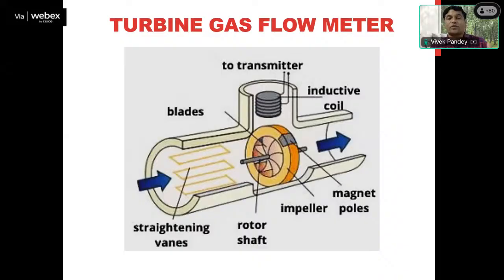And with the gas pressure, the rotor will start rotating, and when the rotor rotates, the magnetic pole will also rotate. And we know very well that when a magnetic pole is rotating, indirectly the magnetic field is rotating, and this magnetic field will interact with the inductive coil connected near the rotor, and that inductive coil will then produce a small voltage, or you can say a voltage pulse. Now these voltage pulses are directly proportional to the quantity of gas passing through the rotor or the turbine. These voltage pulses are then processed, and they give the information about the quantity of gas passing through this gas meter. So this is another technology which is very commonly used in gas measurement.